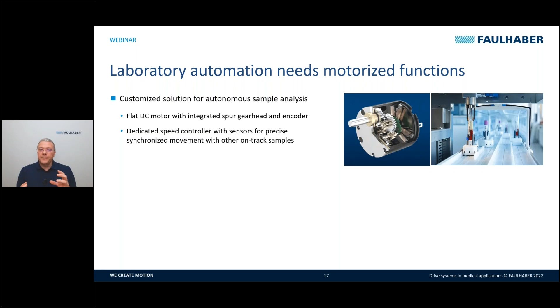We also have a gripping function with variable force in order to grab delicate objects, delicate samples, tubes for example. Even in this case, we have DC brushless or stepper motors from 8 to 16 millimeters. In this case, this is a 10 millimeter motor with gearhead and encoder. We have compact drive electronics with torque control in order to regulate and control the torque of the motor and the gripping force of the gripper.